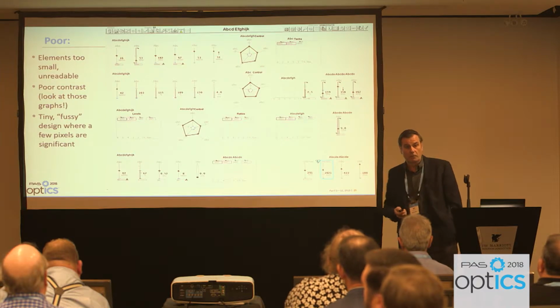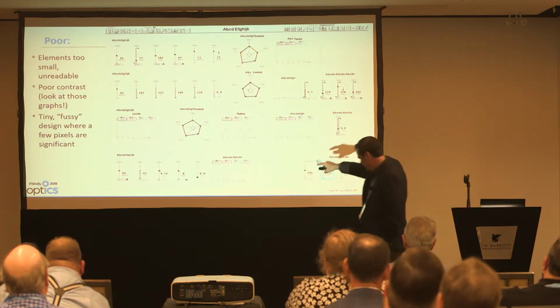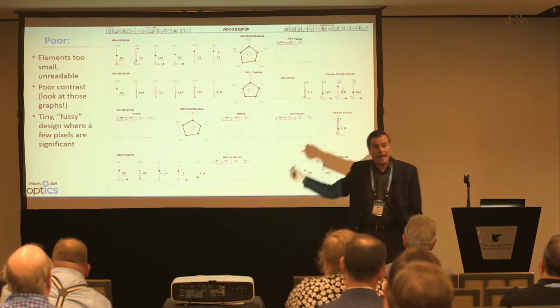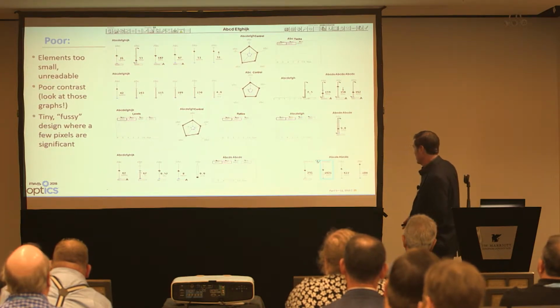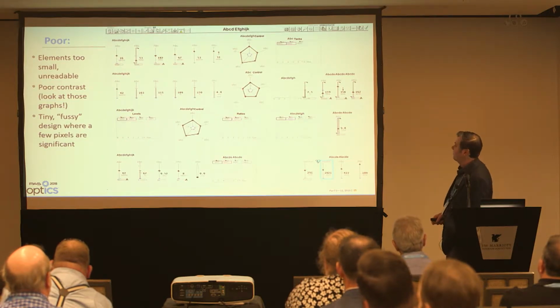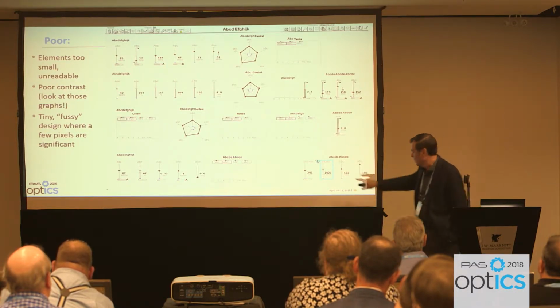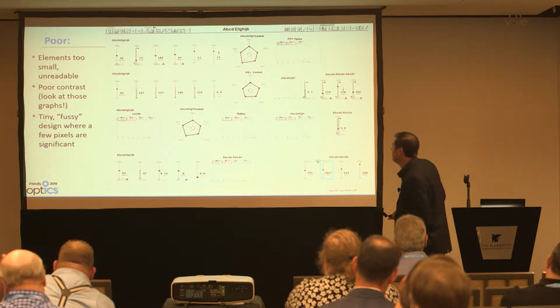Try to make this better. What can we do to make this better? Because now look at this wonderful contrast of this trend line that you're expecting the operator to look at. Can you see that? And again, I have not doctored these. I did not doctor the contrast to make it so poor. Now, do the alarms stand out? This is an alarm, cyan on gray. Not much contrast, and certainly not with a good boundary around it. I'll show you another example of that.